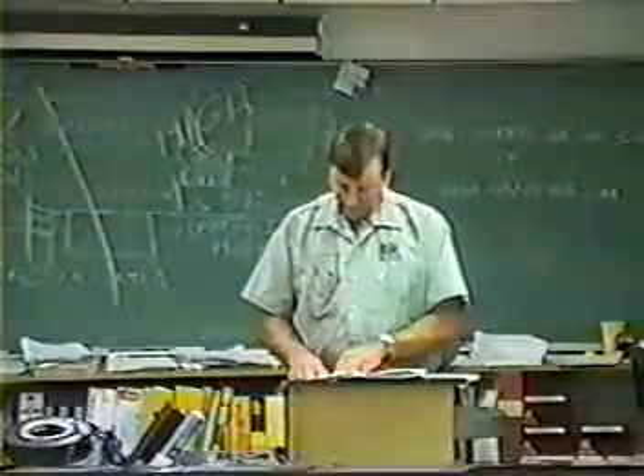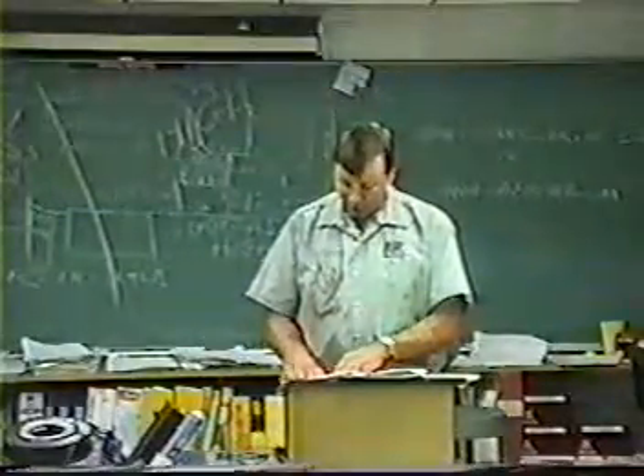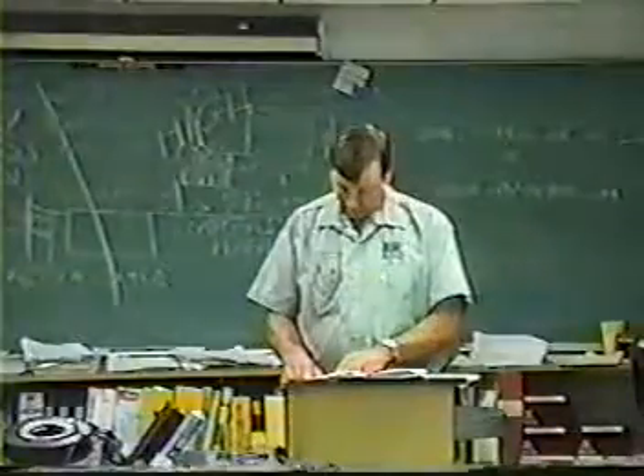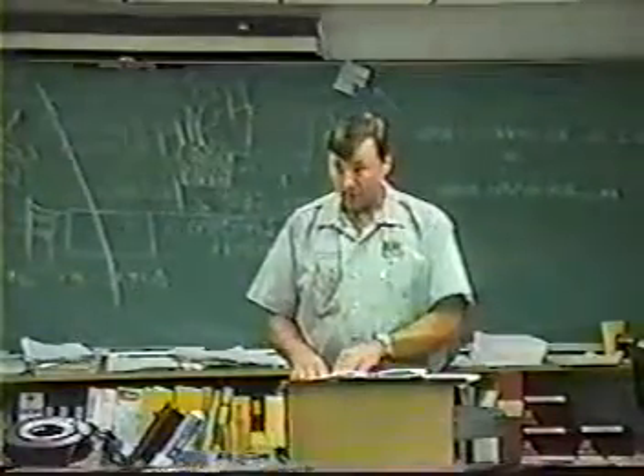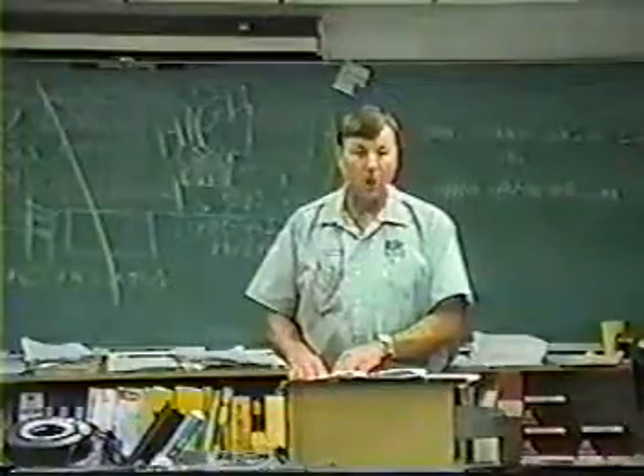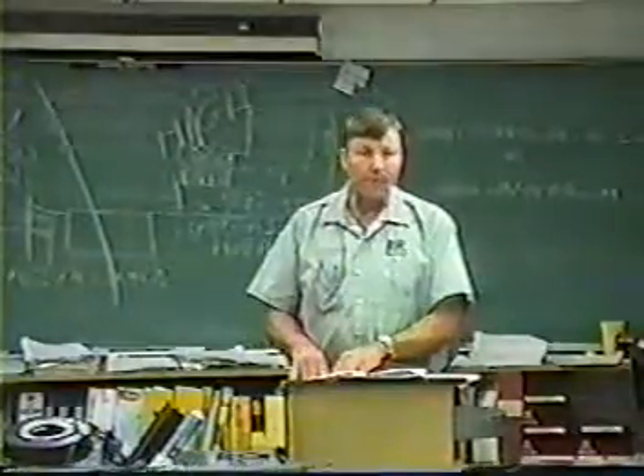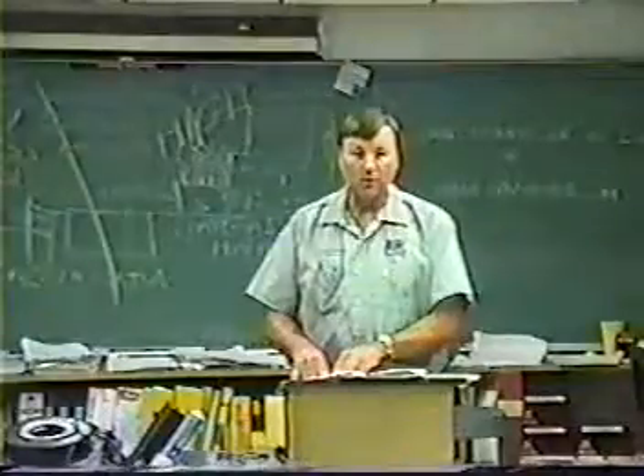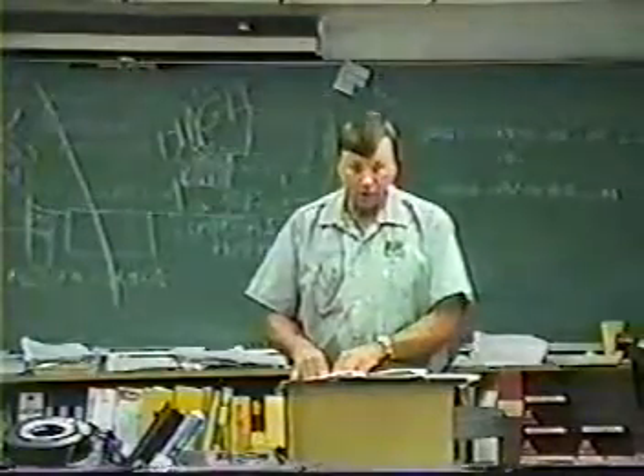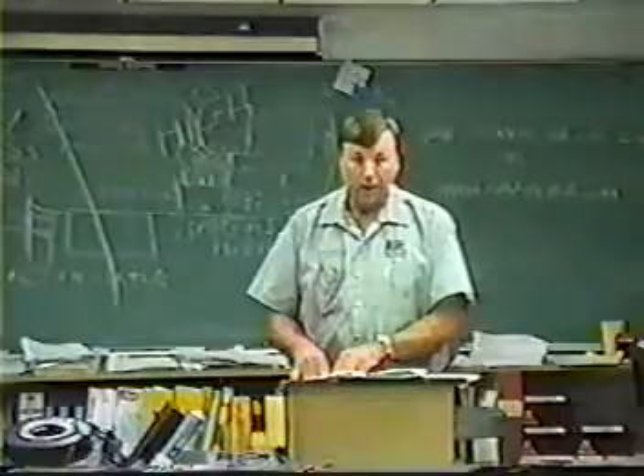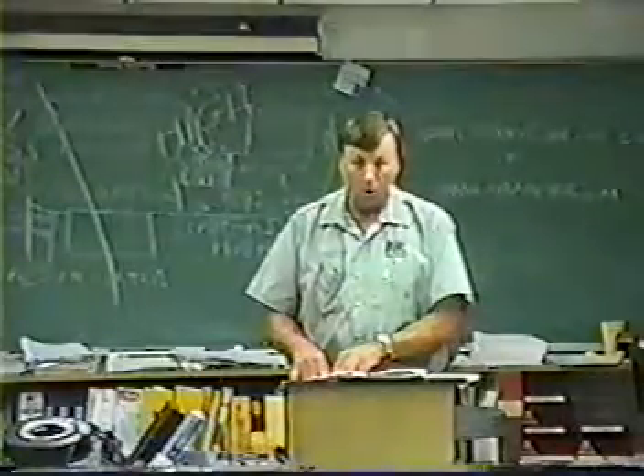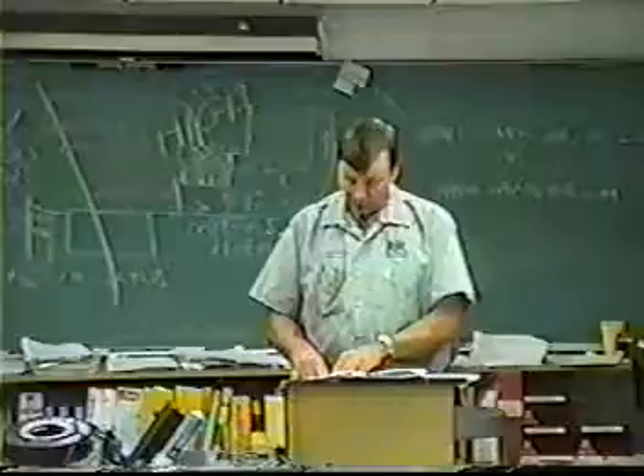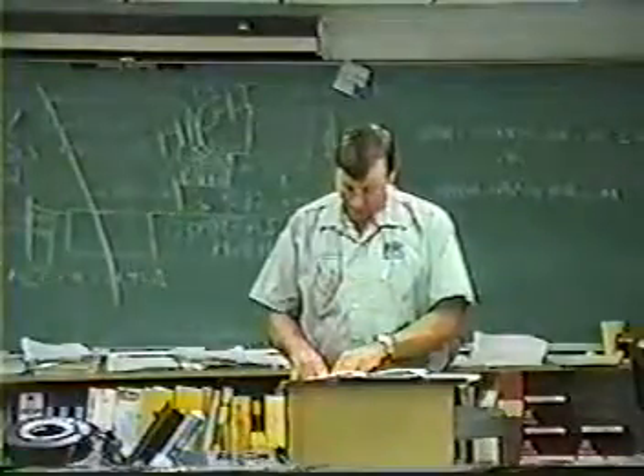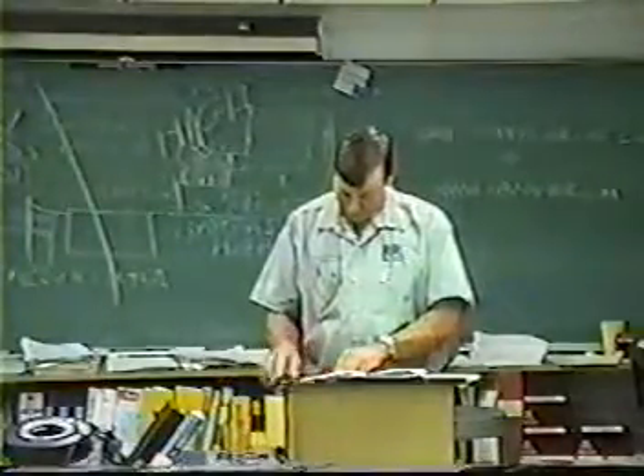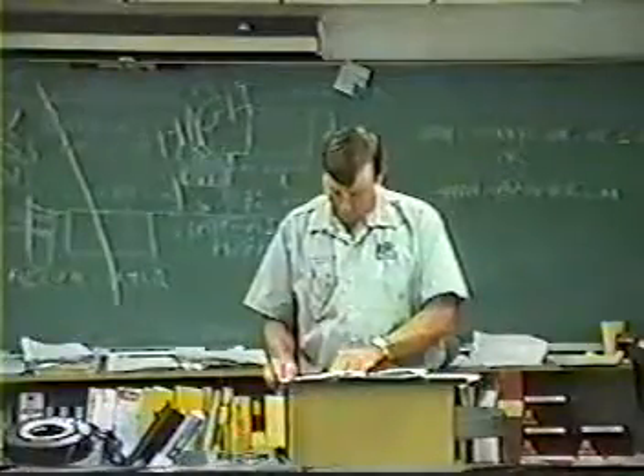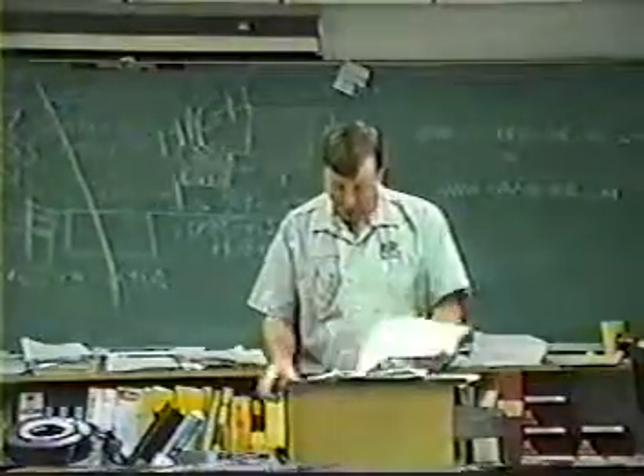Number 73. R134a is a drop-in replacement refrigerant for R12. It's not a drop-in. You cannot use 134a as a drop-in refrigerant. You have to retrofit it. You have to change your oil, you have to change your metering device, you have to flush the system to get out your old mineral oil and use your replacement oil, metering device, and dryer.